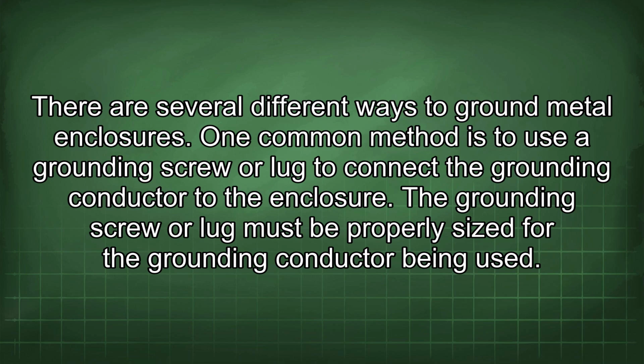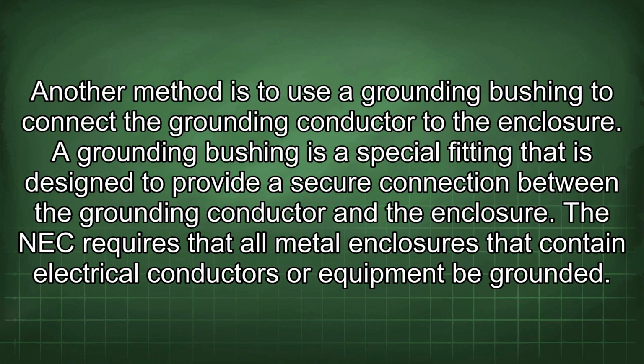There are several different ways to ground metal enclosures. One common method is to use a grounding screw or lug to connect the grounding conductor to the enclosure. The grounding screw or lug must be properly sized for the grounding conductor being used. Another method is to use a grounding bushing to connect the grounding conductor to the enclosure. A grounding bushing is a special fitting that is designed to provide a secure connection between the grounding conductor and the enclosure.